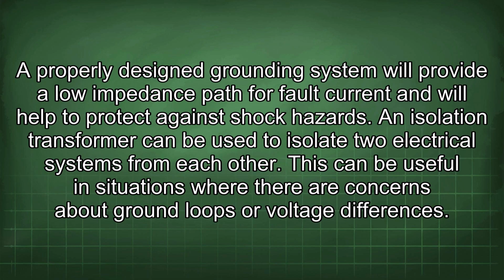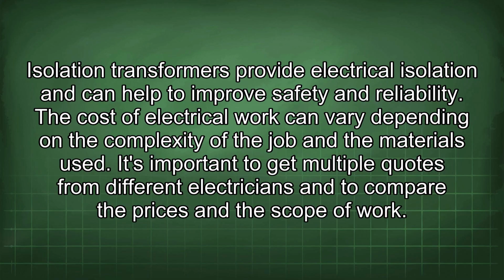A properly designed grounding system will provide a low impedance path for fault current and will help to protect against shock hazards. An isolation transformer can be used to isolate two electrical systems from each other. This can be useful in situations where there are concerns about ground loops or voltage differences. Isolation transformers provide electrical isolation and can help to improve safety and reliability.